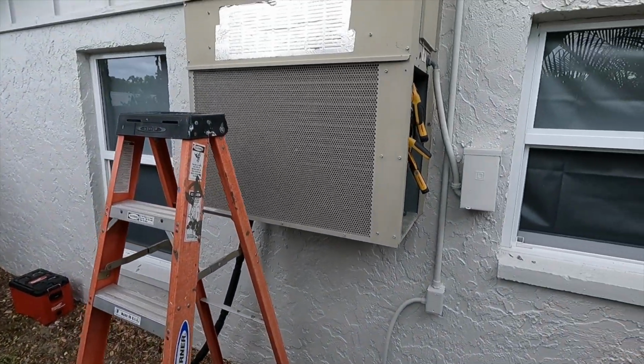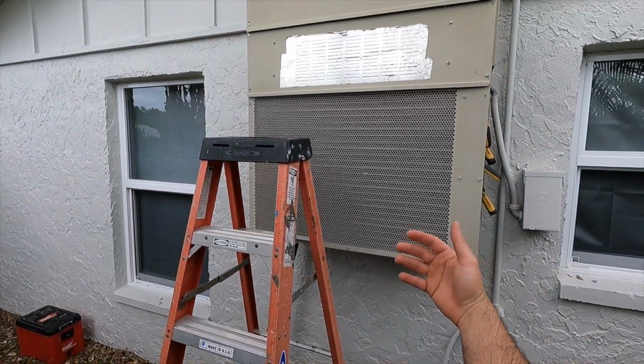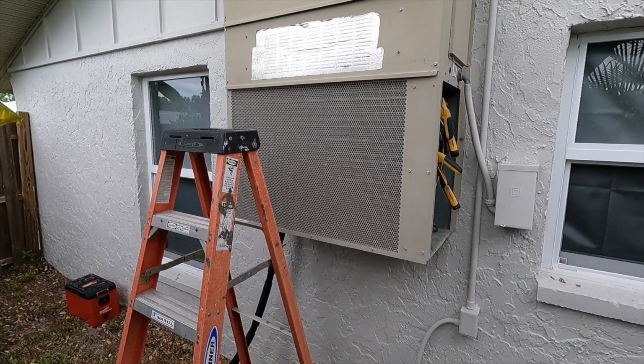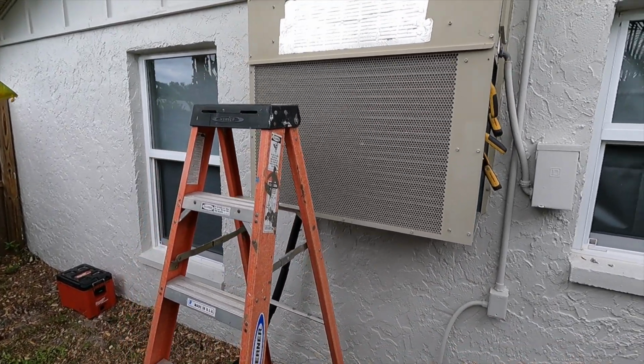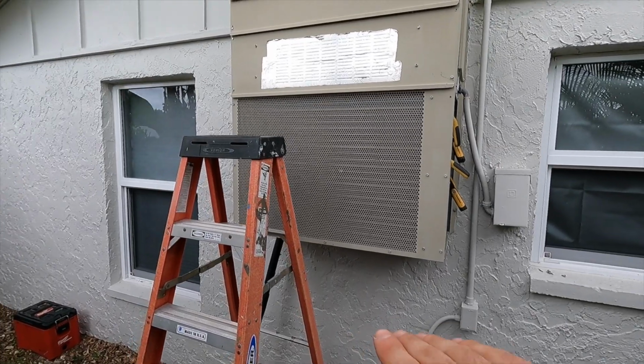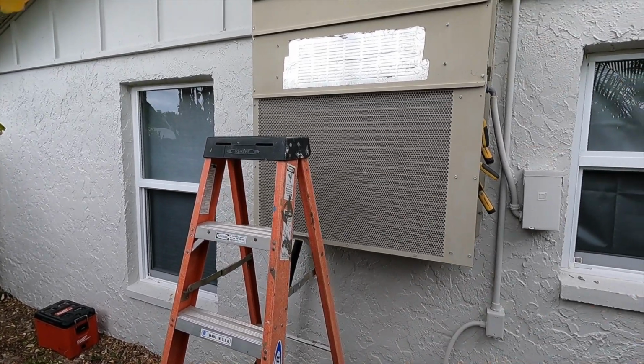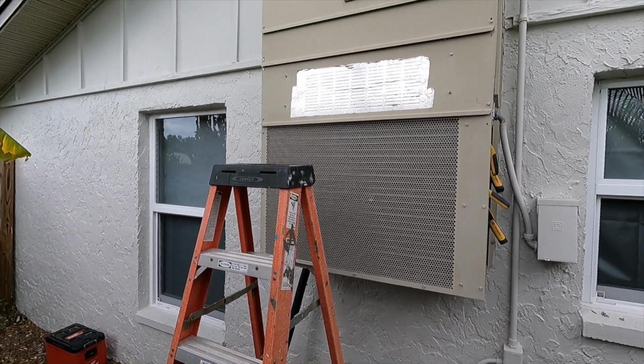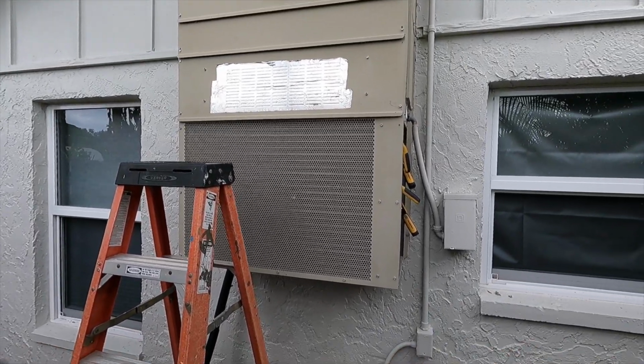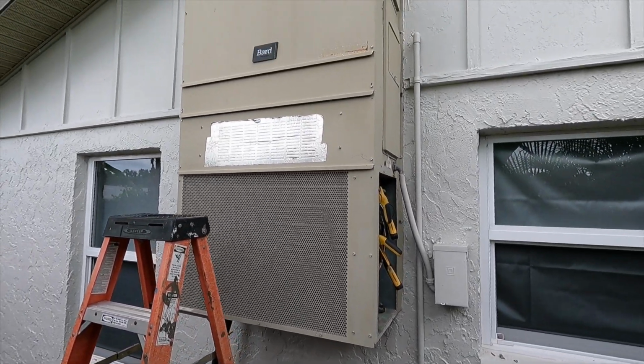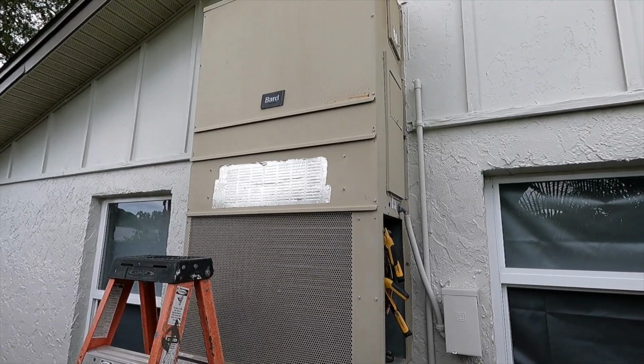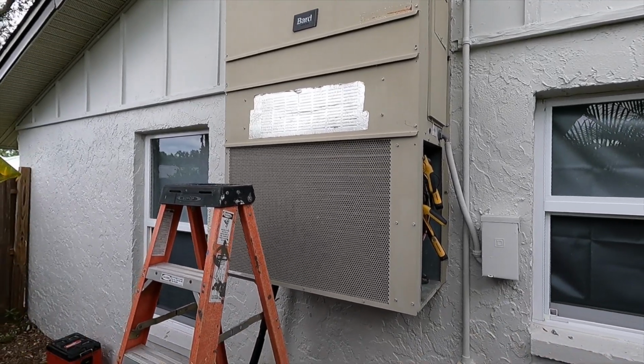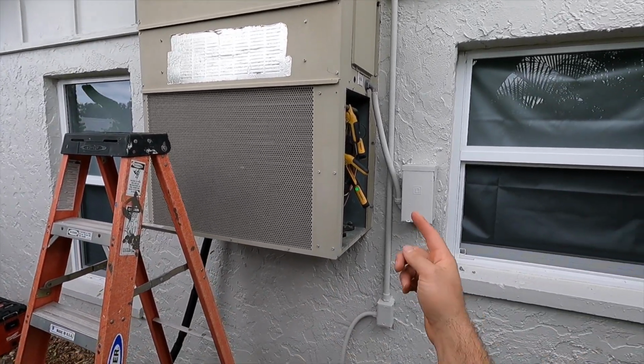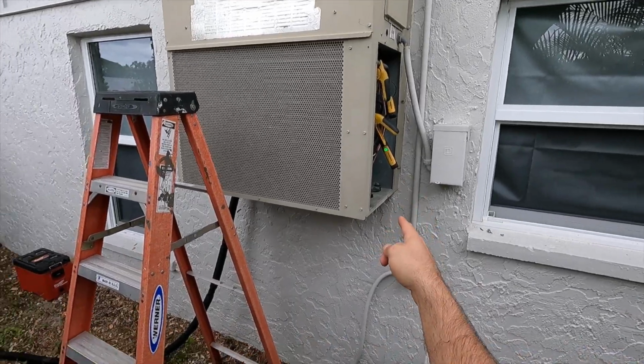Again, the air is being drawn through the sides and then pushed across the outside of the coil, versus our typical units where we see the air drawn through the coil and then rejected out the top. You got that on your standard package units and your split systems. Mini splits, they all work that way, but these BARD wall mounted package units draw through the side, blow out the front. And again, we're drawing air over the compressor, so another heat source.